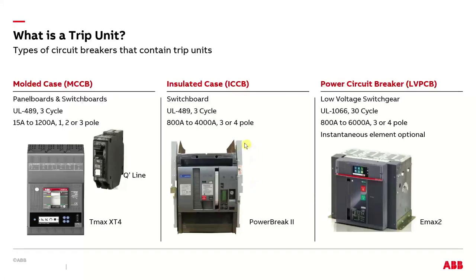Now, the thing you need to know about it is that it's UL489 listed, so it's only a 3-cycle rated device, just like your molded case. But the ranges it comes in are pretty much similar to the power circuit breaker. And now we get to the power circuit breaker, LV PCB. That's primarily in switchgear construction, and its listing is UL1066. It's a 30-cycle rated device.